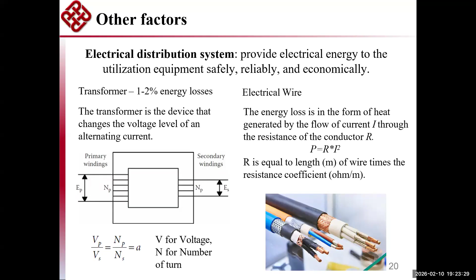Here is a very simple example of an energy loss cost calculation for an electricity line. For example, if we want to calculate the annual energy loss cost of the electrical wire on a 400 meter branch that feeds a load of 16 amp, we assume that the resistance of the wire is 0.36 ohm per 100 meters, the load is used 10 hours per day and 250 days per year, and the cost of electricity is 0.1 per kilowatt hour.